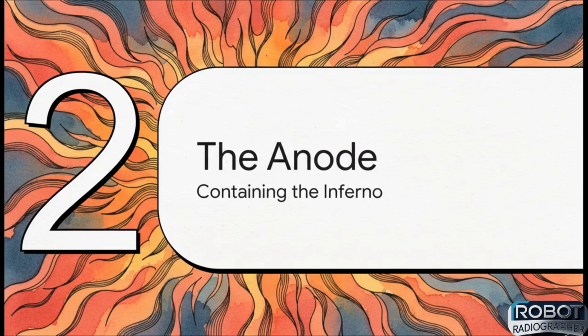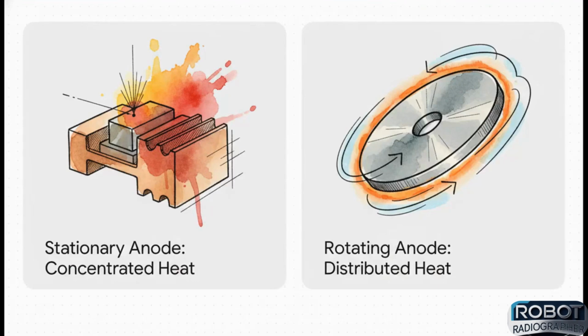All right, so let's trace this whole system, starting right at ground zero. To really get how an X-ray machine stays cool, we have to start where that fire is born, the anode. You can think of this component as the first line of defense, engineered to take that initial punch and contain the inferno. Now, early and lower power machines, like the kinds you'd find at the dentist, use what's called a stationary anode. The heat just hits one spot and then gets pulled away into a big block of copper. But for the heavy-duty stuff, that is just not going to cut it.